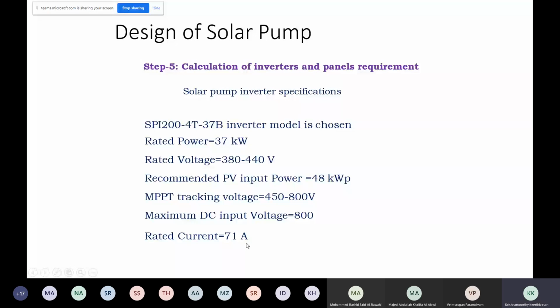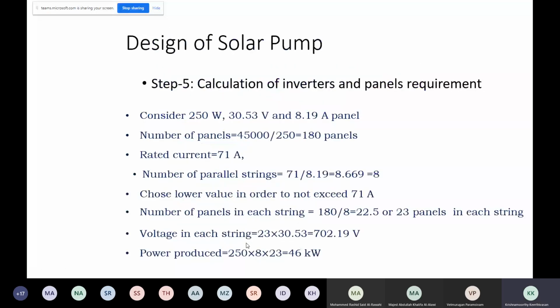Now see the rating of each panel. Each panel gives you 250 watts and the voltage rating is 30 volts. Current is 8 amps. Now you are designing. Total requirement is 45,000 divided by 250 watts. This is the calculation you have to do as an engineer.